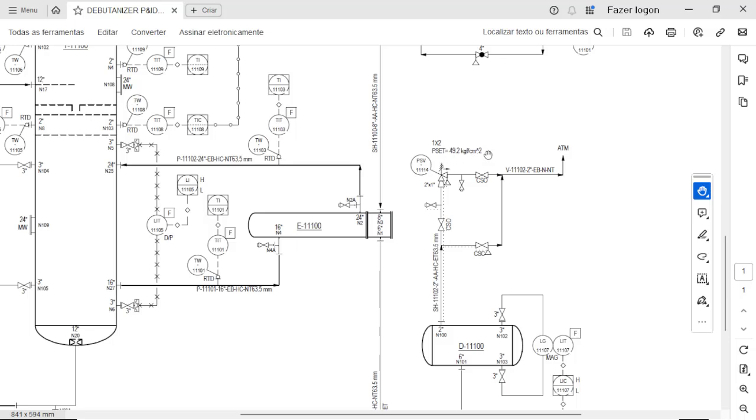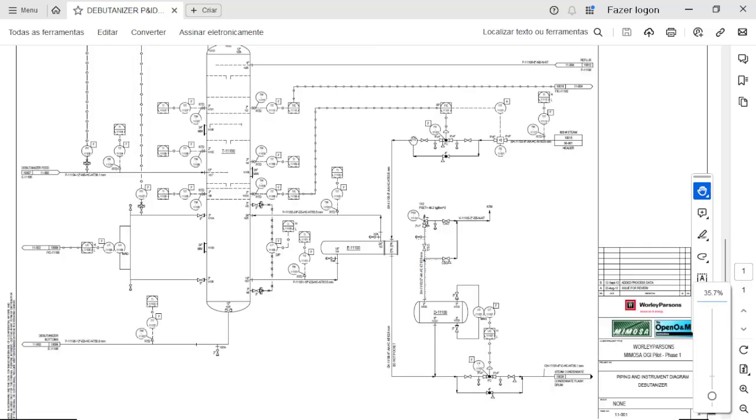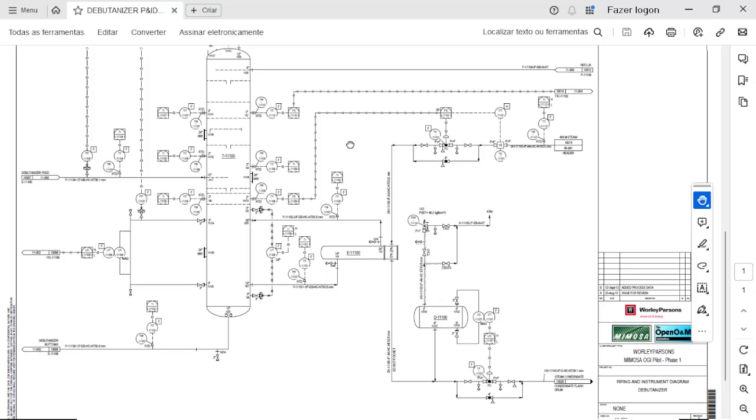It is important to have the opening set point in the drawing because the operator or the commissioning team are able to verify in the field if the information shown in the P&ID matches what was calibrated in the field.